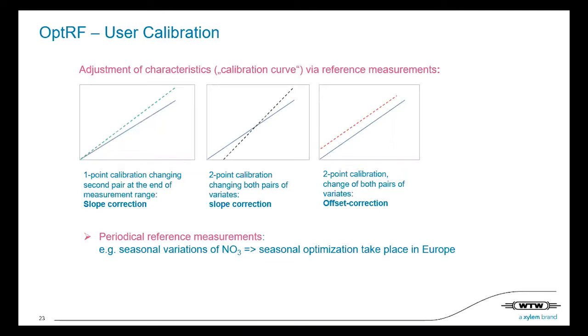Now, with the reference and the optical reagent-free adjustment, you can simply adjust this background calibration curve. If you do only a one-point calibration, like in usual routine analysis, you do a slope correction. If you do a two-point calibration, this can be done in both ways: either a slope correction, or sometimes a so-called offset correction, meaning you shift it just a little bit from the background curve. This sounds difficult, but we have a helping tool, as we'll see in a second.